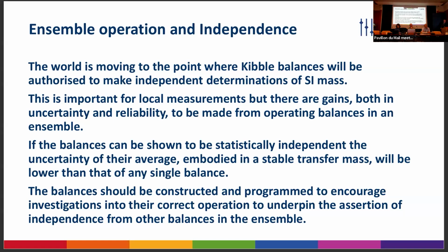You get a gain in uncertainty if they're independent, and reliability if, say, one breaks, you've still got others to depend upon. You've got to be able to show that the balances are statistically independent, and the uncertainty of the average in a transfer mass will be lower than that of any single balance. So it's worth remembering that fact, though people will still be able to just disseminate from their balance.